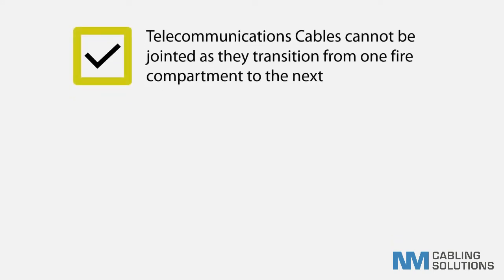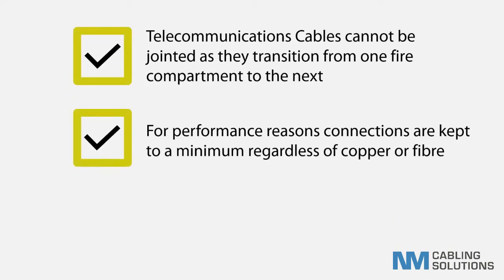Once more, for further clarity, unlike electrical cables, with telecommunications cables connections or joints must be kept to a minimum as each one will introduce an unwelcome signal loss. Therefore telecommunications cables must be of the same Euro class as they transition between fire compartments. Also consider what the evacuation route or space means — it is effectively any space within a building that a human can occupy.